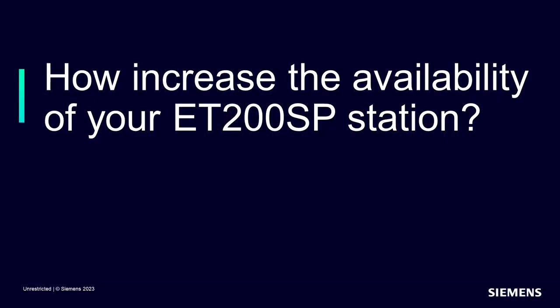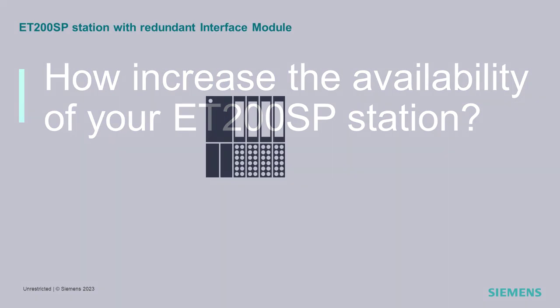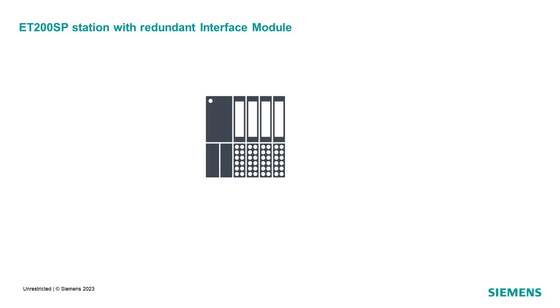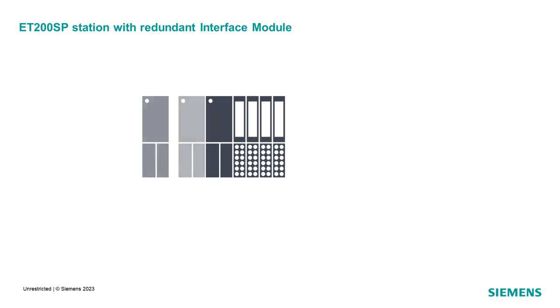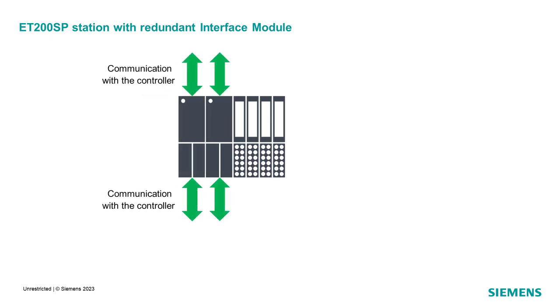To increase the station availability, Siemens has introduced with TIA Portal version 18 a new redundant solution based on PROFINET system redundancy R1. Thanks to an additional interface module, the station can redundantly communicate over two different paths with the controller S7-1500H. If one interface fails, the remaining interface module will take over the communication and therefore there is no impact on the customer process.